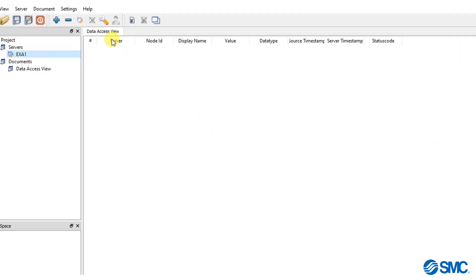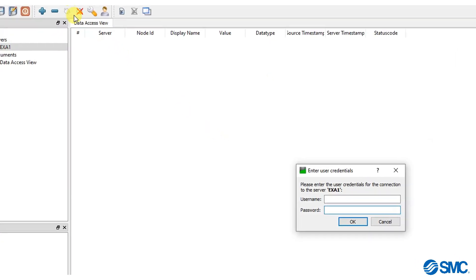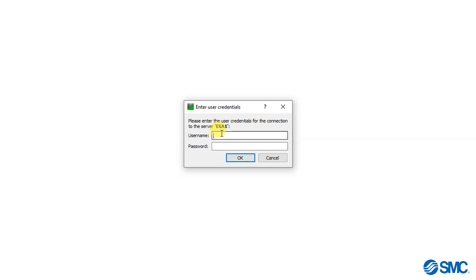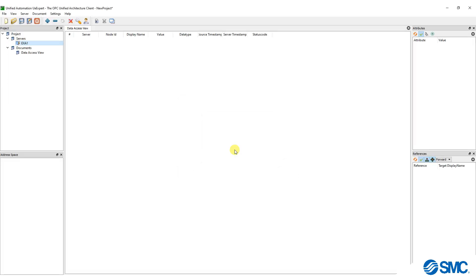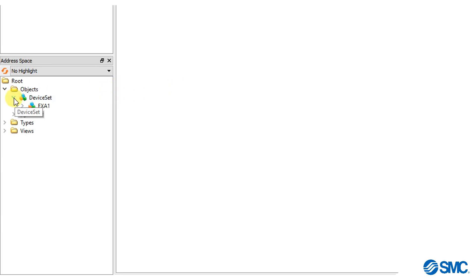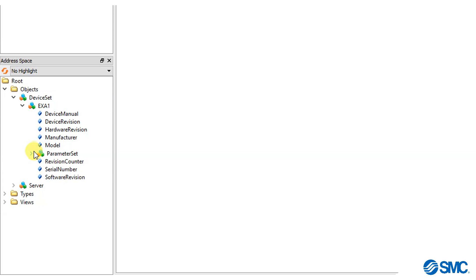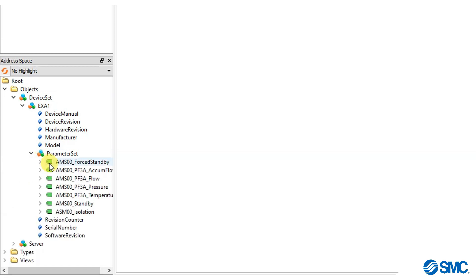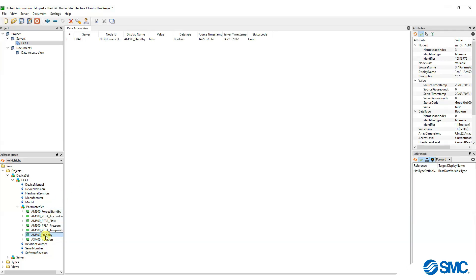In the menu bar, click on the connect icon. A credential window will appear — enter admin, which is the default username and password, and click OK when done. In the address space, you will now find a newly created root folder. Navigate the menu to parameter set, where you can view all the configured nodes that were selected on the system, and drag them to the data access view panel for easy monitoring.